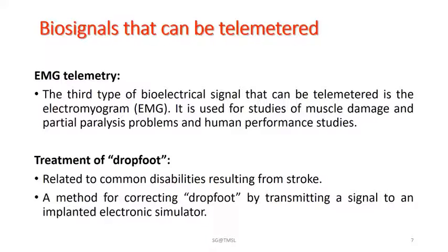Now, this nerve, when it is stimulated, causes the muscles in the lower forepart of the leg to contract, and after that it raises the foot. Stimulation is automatically cycled during this process by a heel switch that turns the transmitter on and off so as to approximate the normal activity of these muscles during the gait operation.